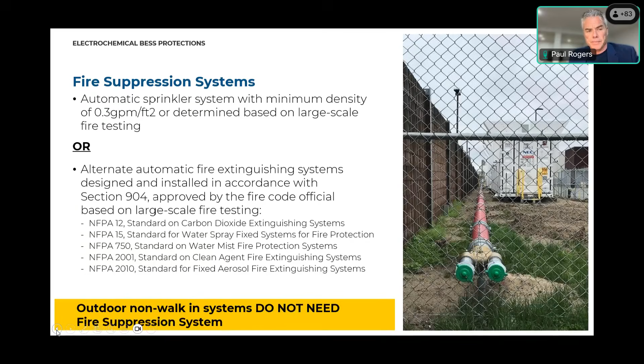Indoor systems, here's what it would look like: a water system and a sprinkler system, which has to be 0.3 gallons per minute per square foot, as mentioned before. If there's a gaseous system, all of these things still need to be inspected to make sure they work for game day. For the gas ones, there are special inspections we've seen performed. In some cases, you could have both an aerosol suppression system and a water system, and the aerosol system may activate before the sprinkler system, trying to reduce heat so the sprinkler system isn't activated as a result.